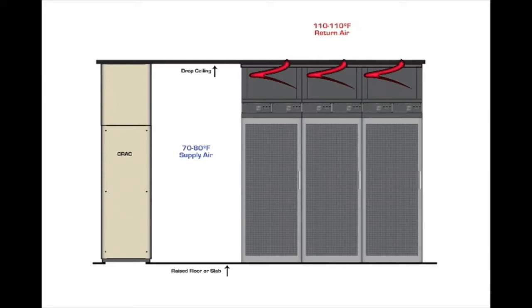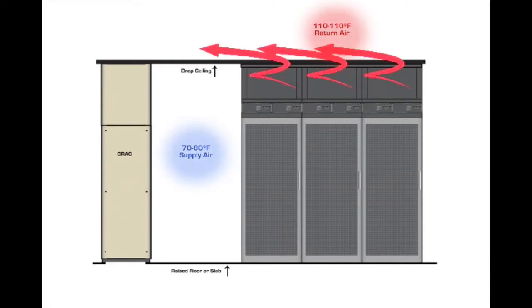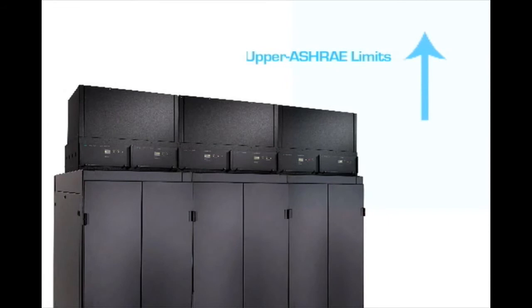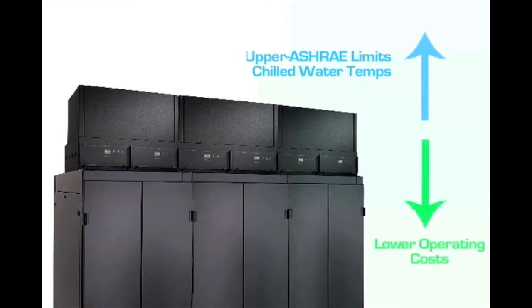By isolating the supply from the return air, total separation is achieved, allowing CRAC units to operate at maximum efficiencies. This active rack containment cooling method is scalable to 30 kW per enclosure. Addressing the green-focused facility, users can reduce energy consumption by raising supply air temperature to upper ASHRAE limits. The total separation of supply and return air allows higher supply air temps, which allows for chilled water temps to be raised, saving additional energy on operating costs.